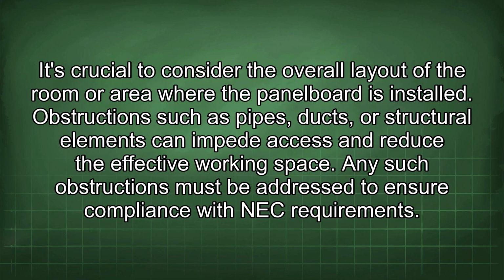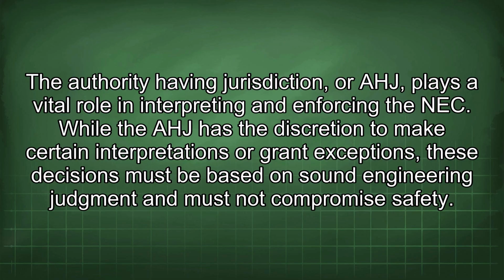It's crucial to consider the overall layout of the room or area where the panelboard is installed. Obstructions such as pipes, ducts, or structural elements can impede access and reduce the effective working space. Any such obstructions must be addressed to ensure compliance with NEC requirements. The authority having jurisdiction, or AHJ, plays a vital role in interpreting and enforcing the NEC. While the AHJ has the discretion to make certain interpretations or grant exceptions, these decisions must be based on sound engineering judgment and must not compromise safety.